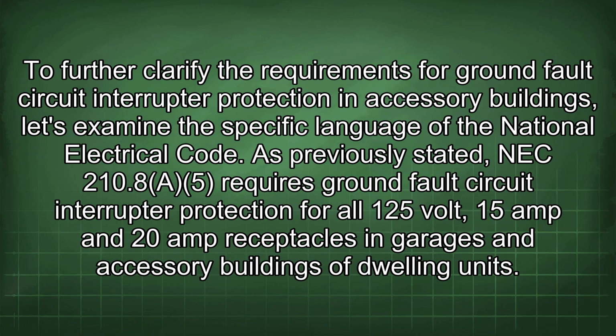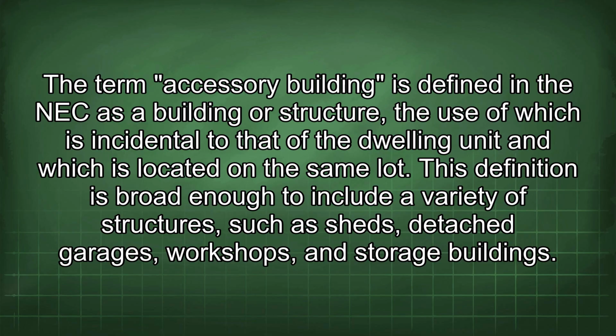To further clarify the requirements for ground fault circuit interrupter protection in accessory buildings, let's examine the specific language of the National Electrical Code. As previously stated, NEC 210.8(A)(5) requires ground fault circuit interrupter protection for all 125 volt, 15 amp and 20 amp receptacles in garages and accessory buildings of dwelling units. The term accessory building is defined in the NEC as a building or structure, the use of which is incidental to that of the dwelling unit and which is located on the same lot. This definition is broad enough to include a variety of structures such as sheds, detached garages, workshops, and storage buildings.